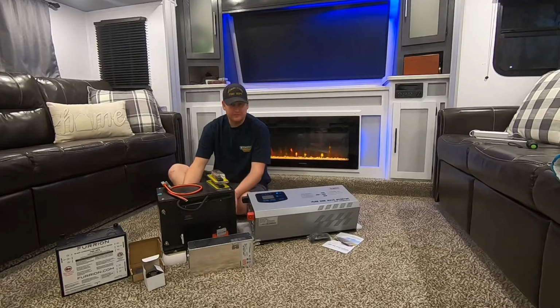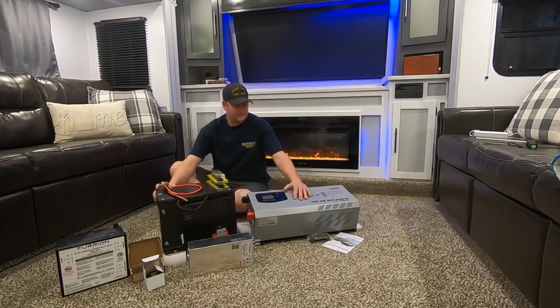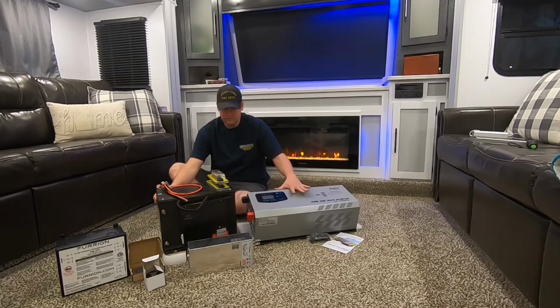It's beyond a difference of 20 amps, it's actually a difference of about 100 amps, because 50 amp RVs have two 50 amp poles, so it's actually 100 amp service, not a difference of 20. Because of that, there's a lot of different equipment you need, since if you watch some of the 30 amp RV guys do their videos, their inverters are quite a bit smaller than this one. So I'm going to run through the equipment I have.